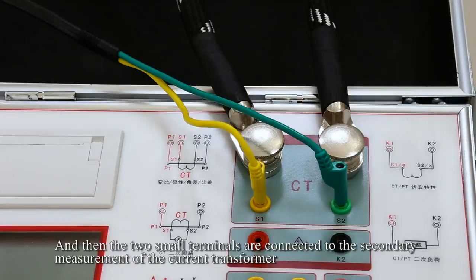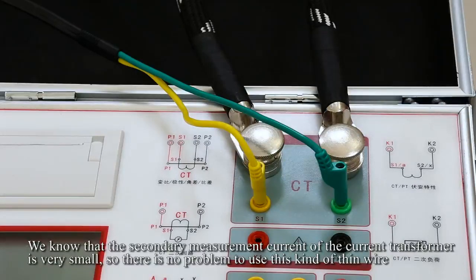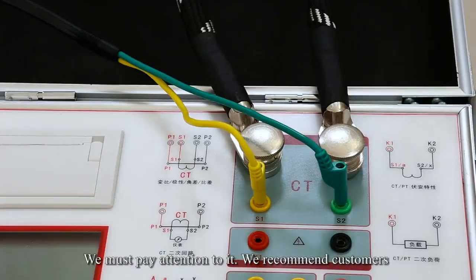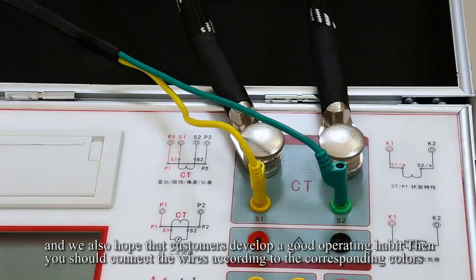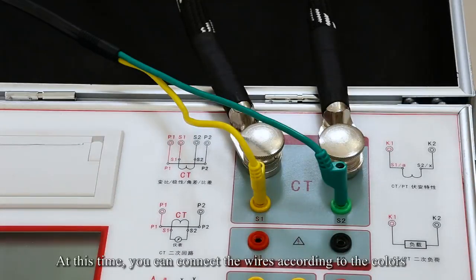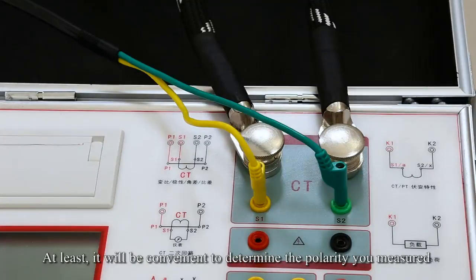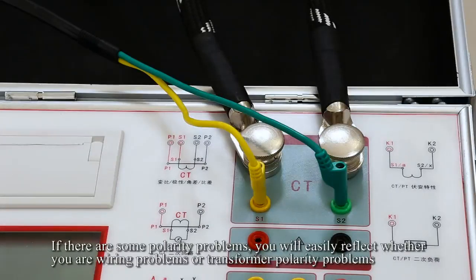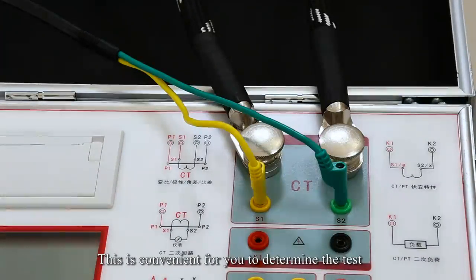Then the two small terminals are connected to the secondary of the current transformer. The secondary current of the current transformer is very small, so there is no problem using the thin wire. We recommend, and hope customers develop, a good operating habit: connect the wires according to the corresponding colors. At least it will be convenient to determine the polarity you measured. If there are polarity problems, you can easily tell whether it is a wiring problem or a transformer polarity problem. This is convenient for determining the test.